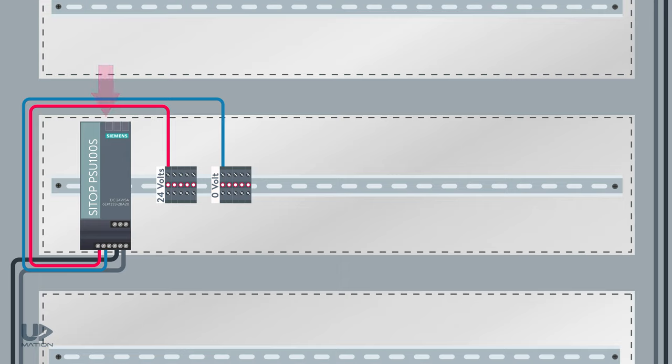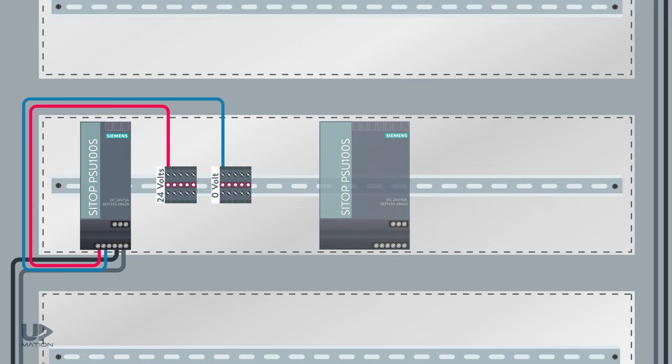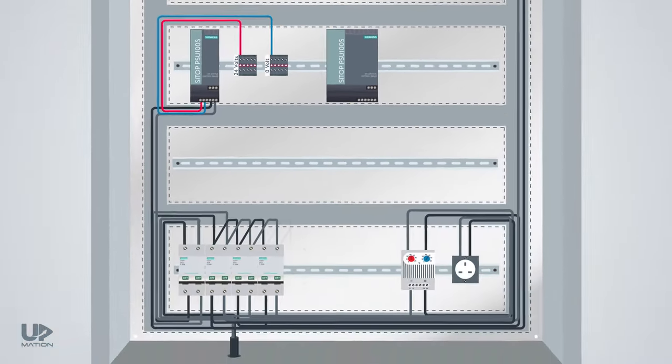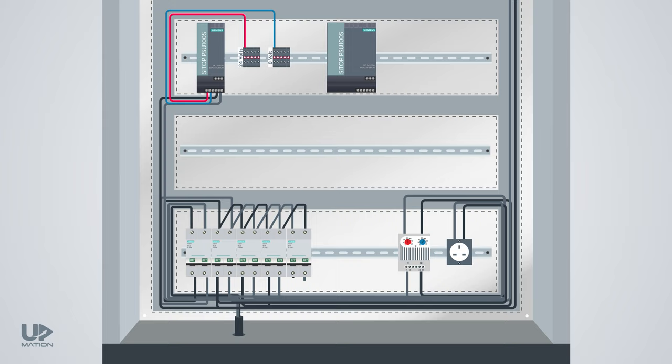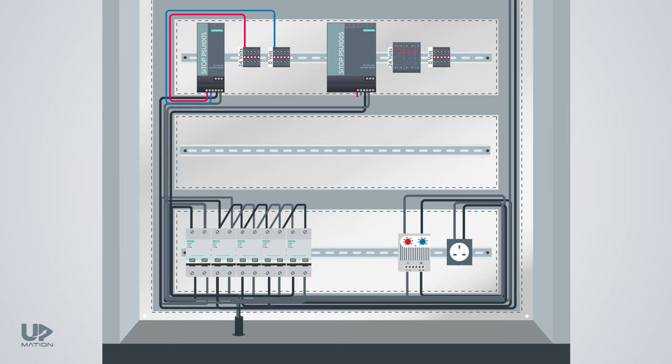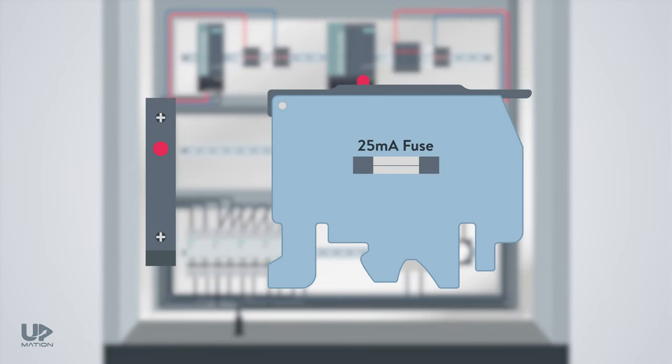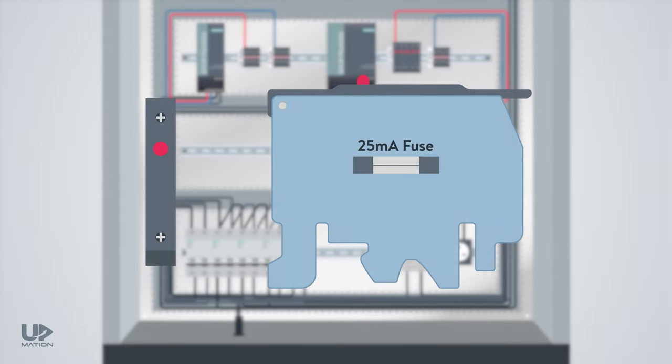Therefore, I should consider a separate power supply with sufficient amperage for feeding the devices at site, such as instrumentation devices. I repeat the same procedure for this power supply, but this time instead of ordinary terminal blocks, I consider some fused terminal blocks to protect the power supply against drawing extra amps by the devices at site. I'll explain that with a practical example in a video about troubleshooting the control panels.